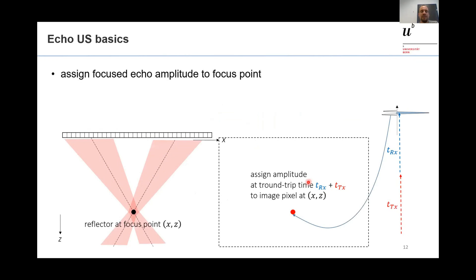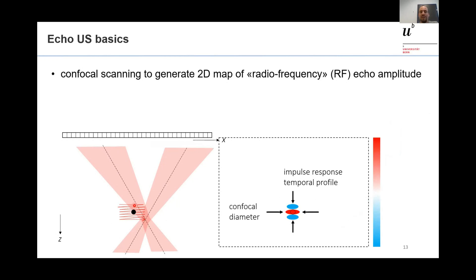Knowing the transmitted and receiving focused beams, we take the summed signal received at the total round-trip time — consisting of the transmit time from array to scatterer plus receive time back to the array. This time assigns the value to a certain depth, corresponding to speed of sound times total round-trip time. By scanning the confocal beams over the imaging plane, we receive an echo response. The diameter is determined by the confocal beam diameter, and the axial profile is determined by the impulse response of the transducer.